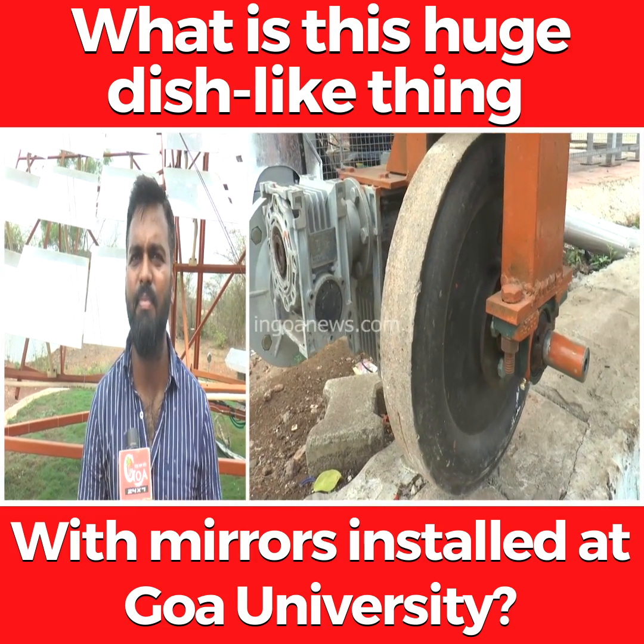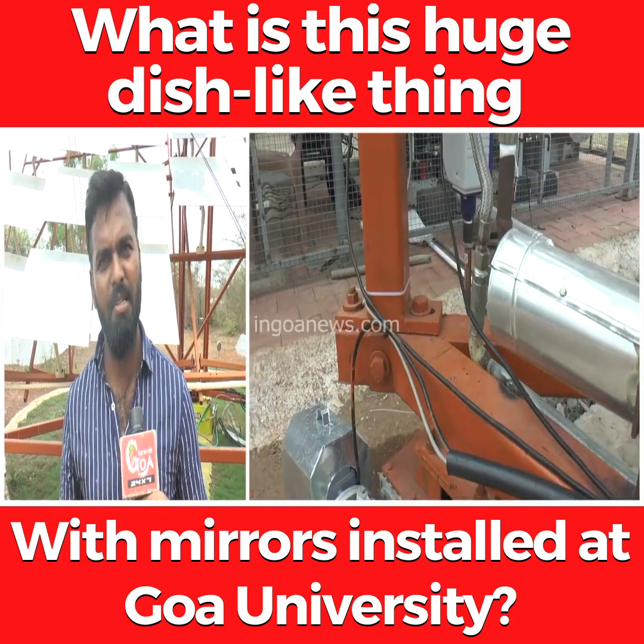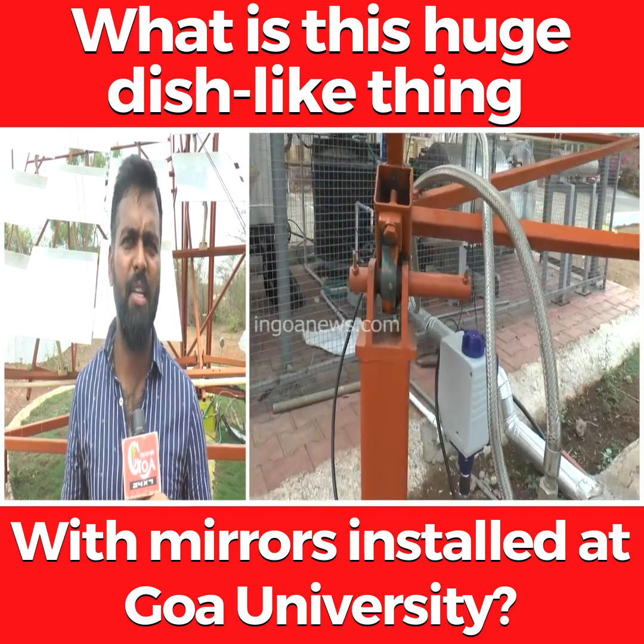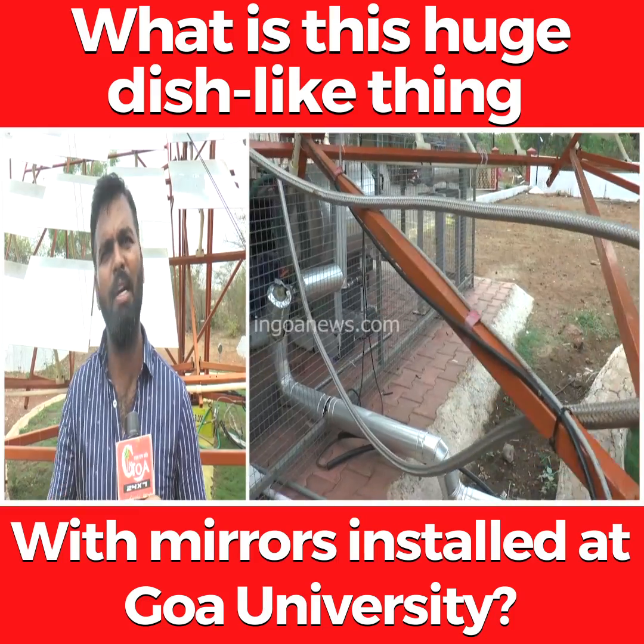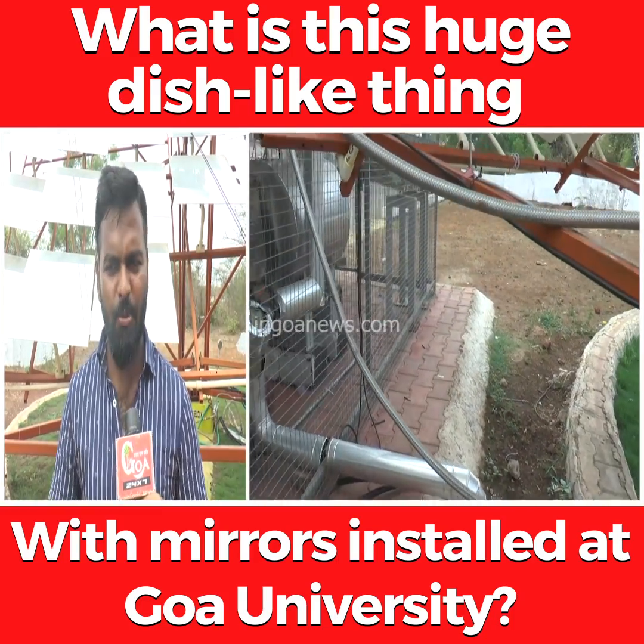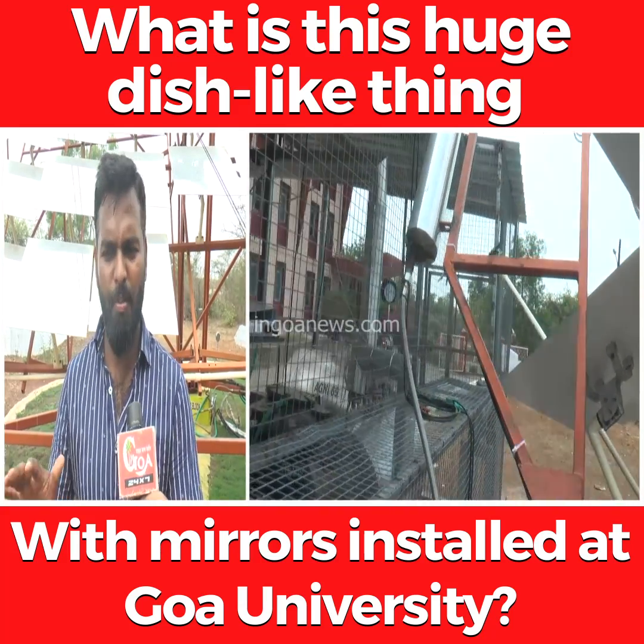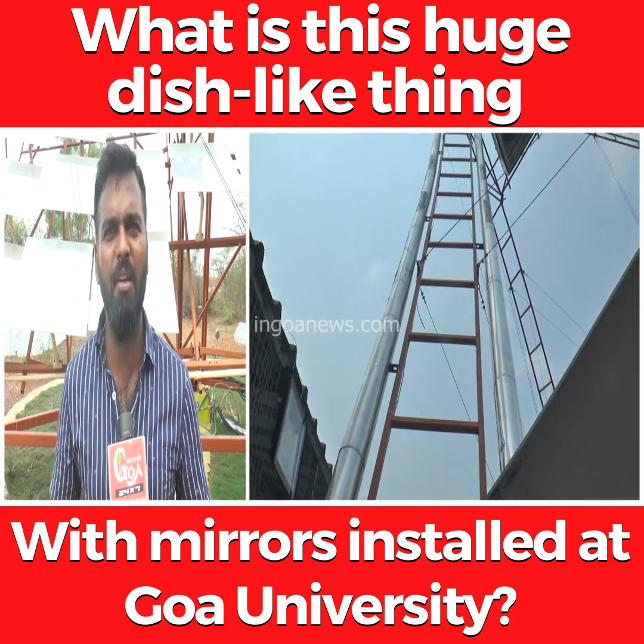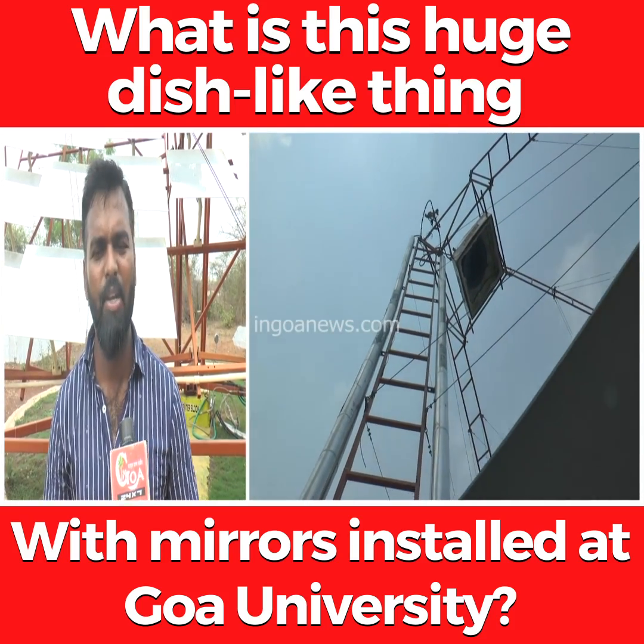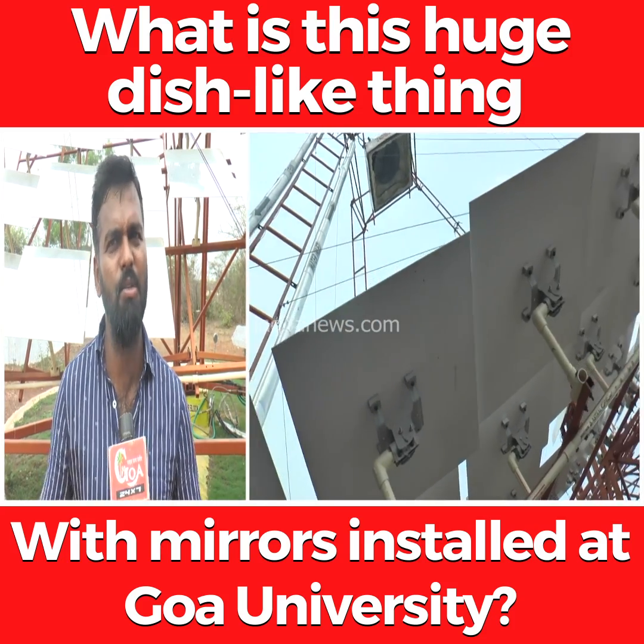For the rainy season, as I mentioned, we have integrated the system with the existing boiler. If there is no sun for 5 to 7 days, the existing system will automatically get activated. So it is basically a hybrid solar-plus-existing-boiler system. In our country, we can expect around 300 sunny days, so almost 70% of fuel consumption can be reduced and offset by solar heat energy.